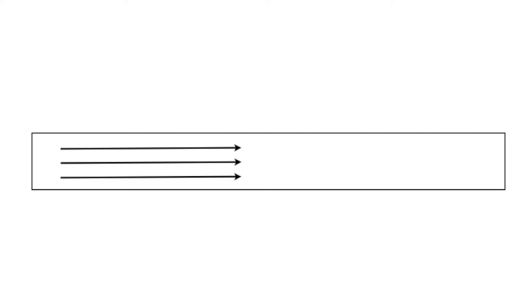Okay, I've got a picture of a line here. This is a suction line. The suction line is one we're most worried about. The liquid line, whereas it does need to be sized, it's all liquid and the liquid contains the oil that lubricates the compressor. So when it's liquid, it's mixed and there's not a problem.